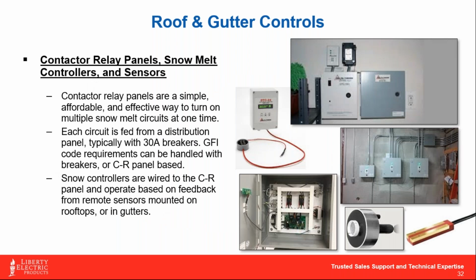Contactor relay panels. This is a very popular system when we're talking about commercial and industrial applications because typically we're looking at more than 2 circuits. It would be anywhere from 4 circuits, 8 circuits, who knows. Contactor relay panels are very simple. We have to bring over each 30 amp breaker from a distribution panel to each one of those circuits on the contactor relay panel. So it does make it a little bit more labor intensive, but very simple as far as its electric operation goes.